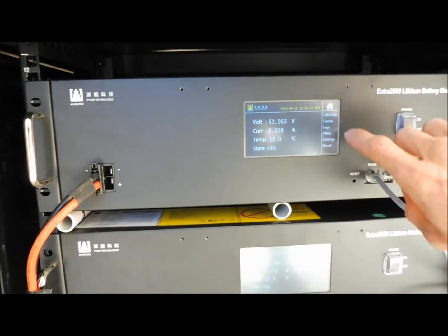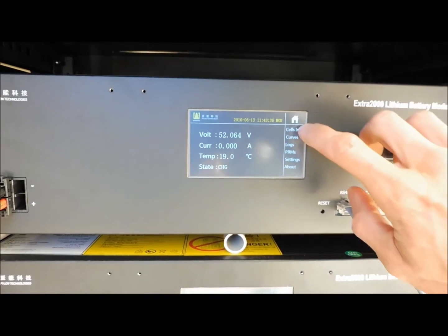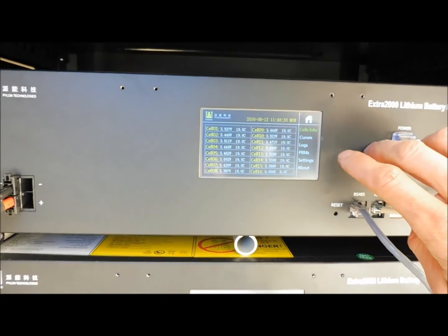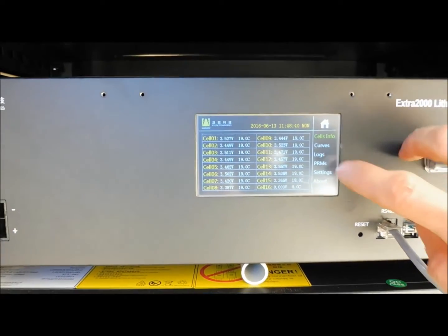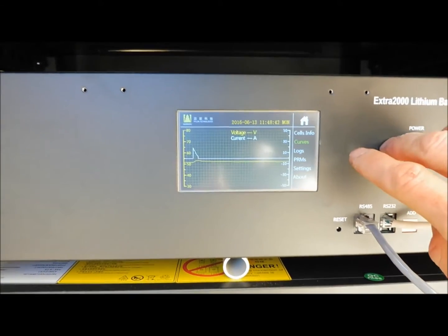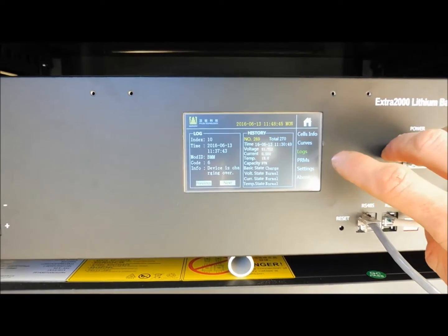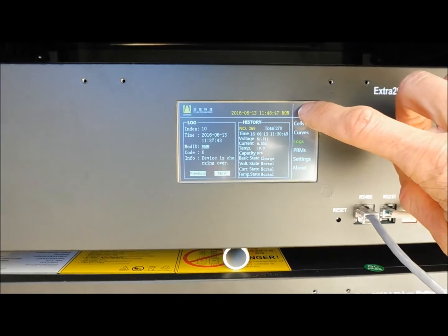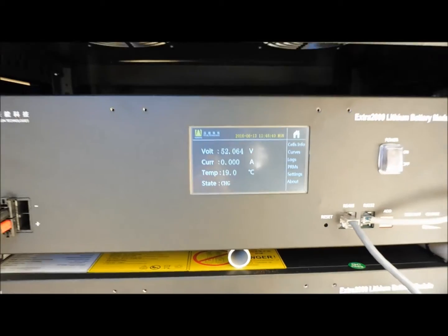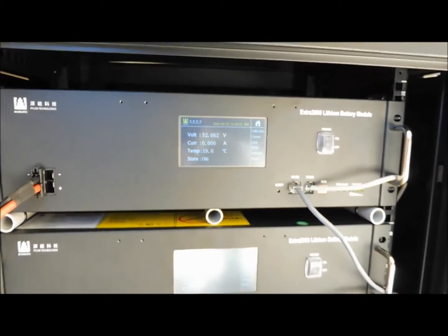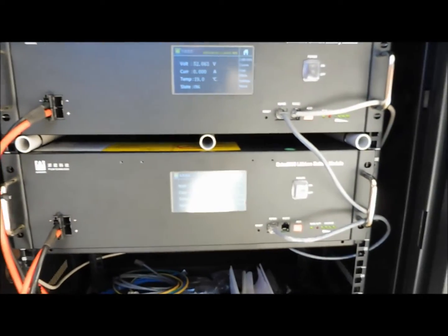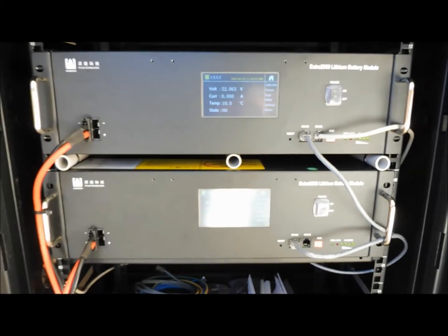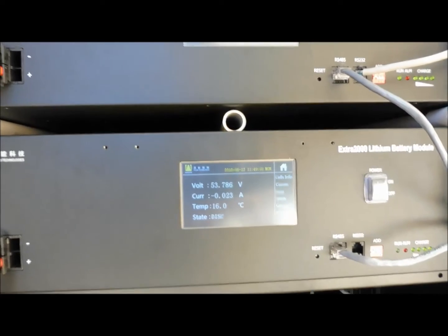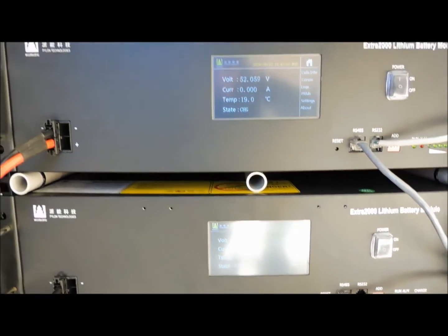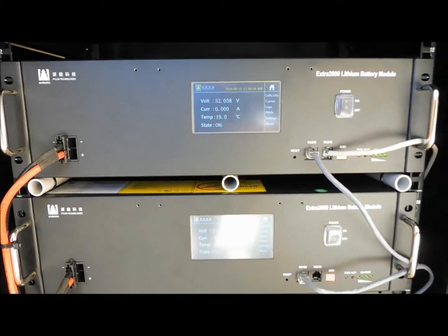Very handy little touch screen. It gives you some information here. I can look at individual cell voltages and temperatures, power curves, logs. It's a very nicely put together battery system, and they link together through communications back to the inverter, so the inverter understands what state of charge the batteries are at, and the voltage, charging current - everything can be set up.